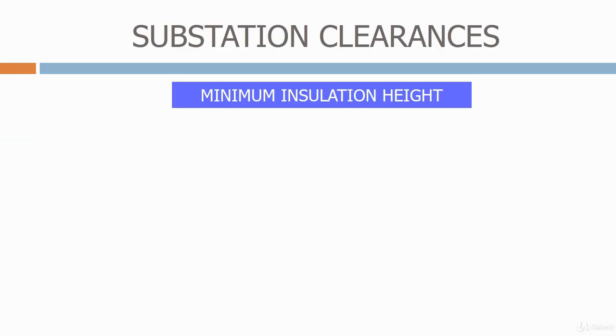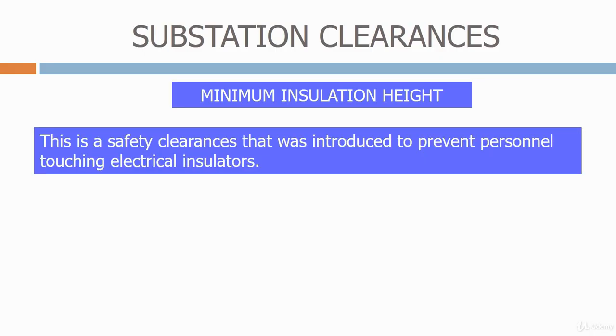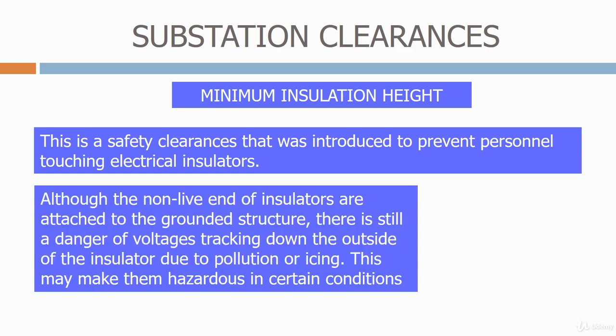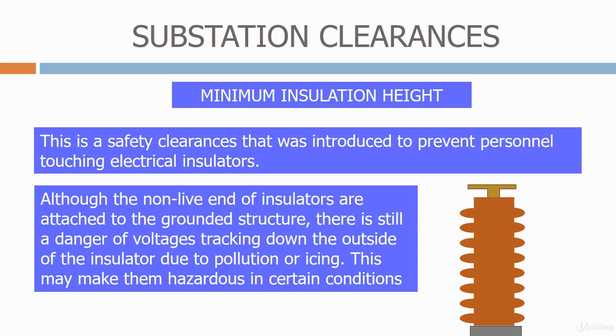The next clearance to consider is the minimum insulation height. This is a safety clearance that was introduced to prevent personnel touching electrical insulators. Although the non-live end of insulators are attached to the grounded structure, there is still a danger of voltages tracking down the outside of the insulator due to pollution or icing. This may make them hazardous in certain conditions. And the last thing we want people to be able to do is to touch the insulator and put themselves in harm's way.